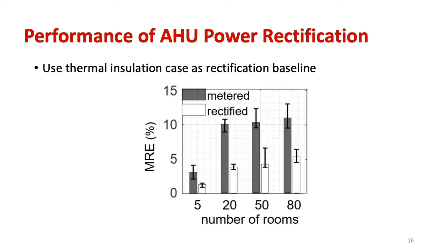First, we evaluate the performance of AHU power rectification. We use the case with thermal insulation as the baseline to evaluate the effectiveness of the rectification. The figures show the mean relative errors of the original AHU power readings and the rectified readings. We can see that the rectified AHU power readings are closer to those under the case with thermal insulation, showing the effectiveness of the rectification.